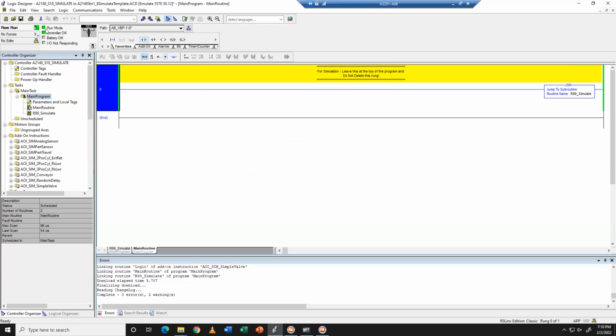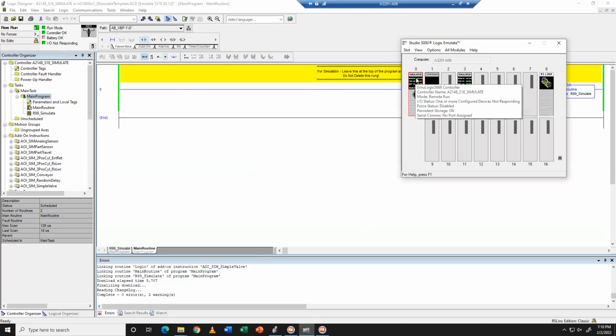And that's going to make everything green. It'll say run mode here. The lights on the processor, there's actually a run button. It'll turn green, telling you it's executing code in some fashion, if the key switch is physically in run. If everybody looks here where my mouse is, when I push this into run mode, you see how that changed states, and it looks like it's physically pointing at run. You will see that if you get online with the controller. If it's in run mode, you cannot put it into program mode, and you can't even make online edits in run mode.